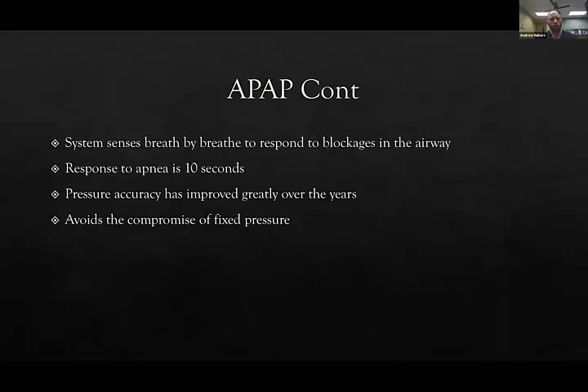So the new style machines, they will wait 10 seconds for this apneic event, and then it will send these slight pulses and puffs of air, little light puffs. And it's really just gauging, are you breathing that in? You breathe it in, system stops. You don't, it starts to increase. And it is waiting for that blockage to be overcome, to have the air come in. The system will then start to tail off, and it'll hang out there before it starts to reduce. And it reduces to, ideally, the baseline, whatever the low-end pressure limit is, so to speak.